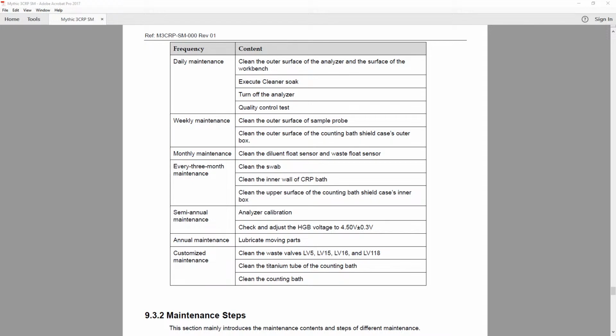As we mentioned previously, right now we will talk a little bit about the maintenance. So the frequency is divided into daily, weekly, monthly, every 3 months or so. As we can see, the daily and weekly ones are the maintenance which should be done by the end user. It's as simple as cleaning the outside surface of the analyzer, executing cleaner soak, and turning off the analyzer. And of course, you need to run the quality control test.